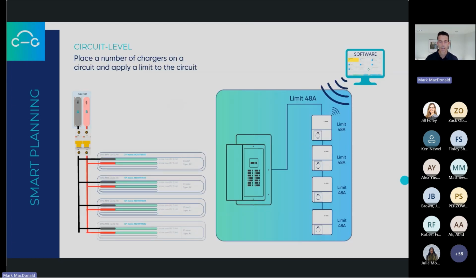This is the most common way. There's multiple ways to do it, but this is the most common way that you would load balance. So the electrical code requires you, if I put one 48 amp charger on one dedicated 60 amp branch circuit breaker, I need to add 48 amps of demand to that building or that load calculation.